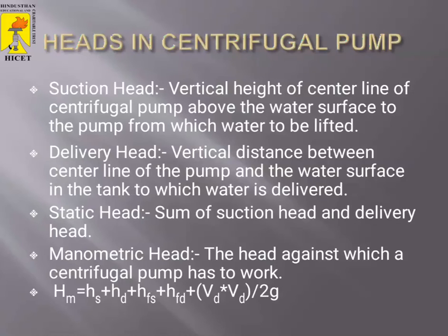The heads in centrifugal pumps are suction head, delivery head, static head and manometric head. Suction head is the vertical height of the center line of the centrifugal pump above the water surface from which water is to be lifted, and delivery head is the vertical distance between the center line of the pump and the water surface in the tank to which water is delivered. Static head is the summation of suction and delivery head, and manometric head is the head against which the centrifugal pump has to work. Hm = Hs + Hd + Hfs + Hfd + Vd²/2g.